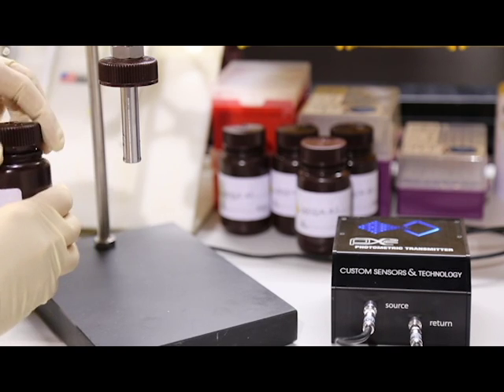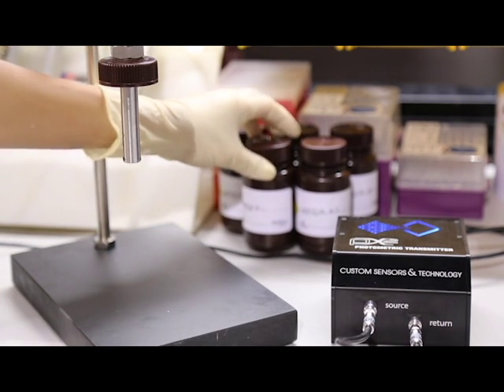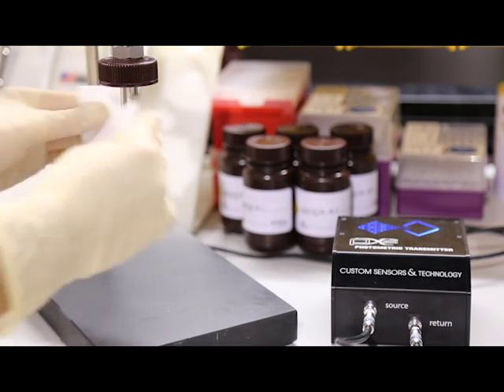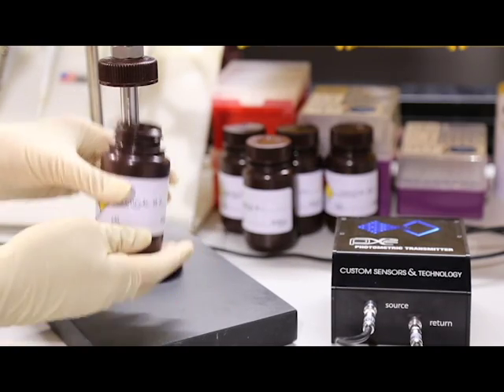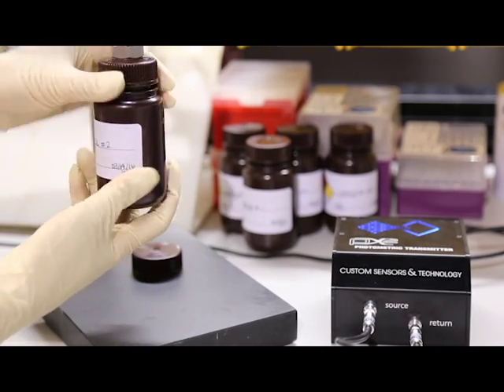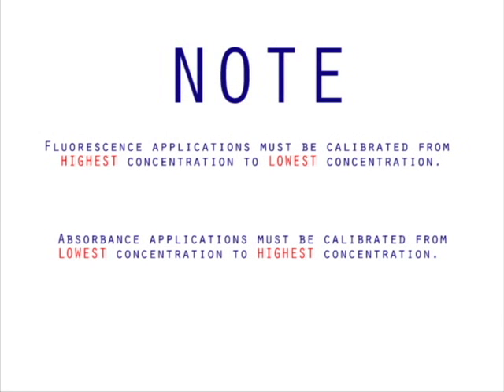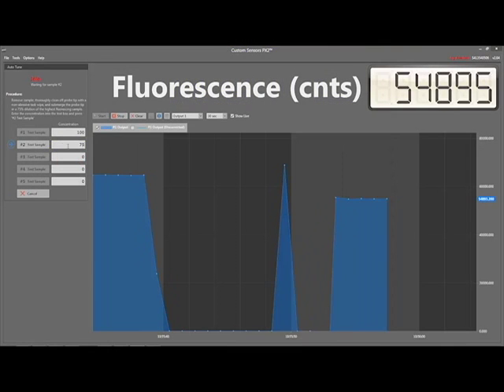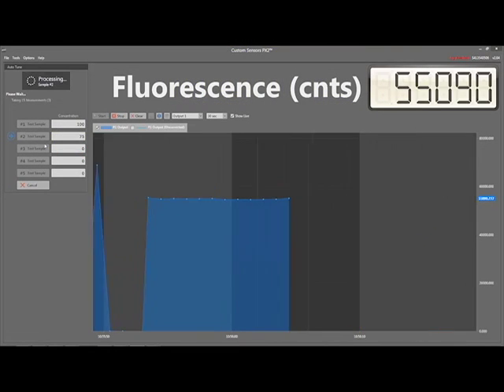Now I am ready for my next sample. I will thoroughly clean off my probe using a non-abrasive task wipe, such as a Kim wipe, before replacing it with my 75% of full-scale sample. The idea is to use the sample with the greatest light output. For fluorescence applications, this will be our most concentrated, highest fluorescing sample, which must be in a dark, opaque bottle. For absorbance applications, this will be the background, or least absorbent sample. I will then repeat the same procedure for samples 2 through 5.